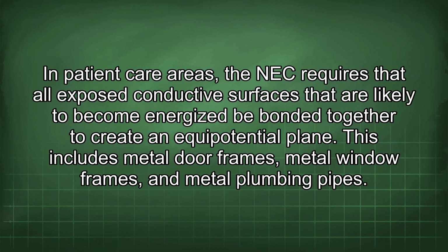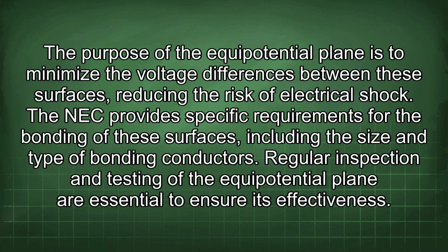In patient care areas, the NEC requires that all exposed conductive surfaces that are likely to become energized be bonded together to create an equipotential plane. This includes metal door frames, metal window frames, and metal plumbing pipes. The purpose of the equipotential plane is to minimize the voltage differences between these surfaces, reducing the risk of electrical shock. The NEC provides specific requirements for the bonding of these surfaces, including the size and type of bonding conductors. Regular inspection and testing of the equipotential plane are essential to ensure its effectiveness.